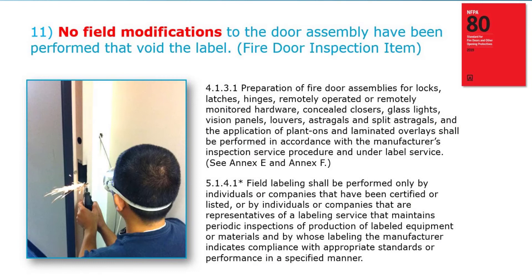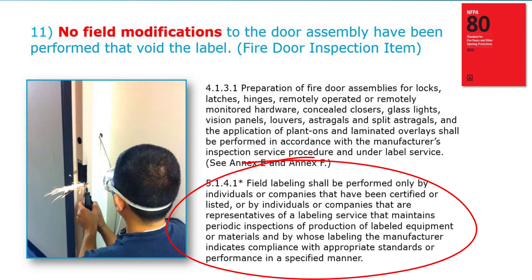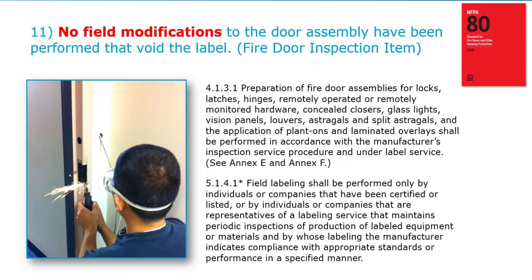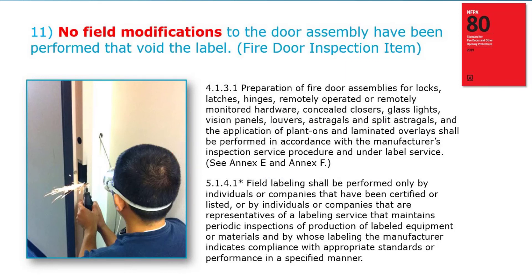When it comes to electric strikes, NFPA 80 inspection item number 11 states that no field modifications to a fire rated assembly have been performed that will void the label. This does not mean we cannot cut an electric strike into the frame — it means the workmanship must be done professionally. Within the codes, it does talk about who is capable of doing those modifications and who can perform inspections. Certain organizations trained and certified by the manufacturer can go in and do field modifications on a fire rated assembly to install a strike into the frame. They have to be trained and certified by the manufacturer, meaning the work must be neat and clean. A local building code official may want to inspect the work after it's done.